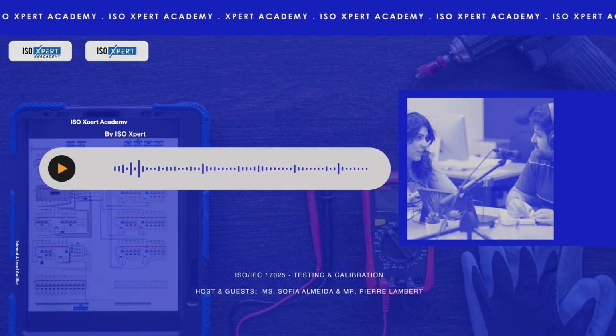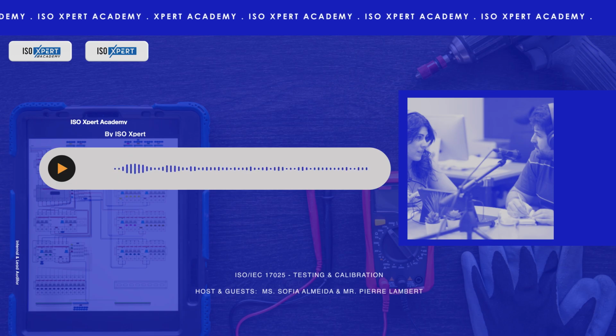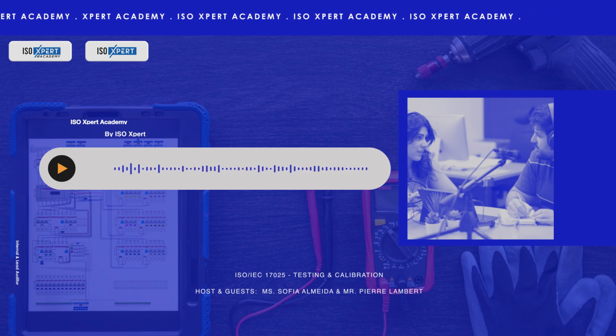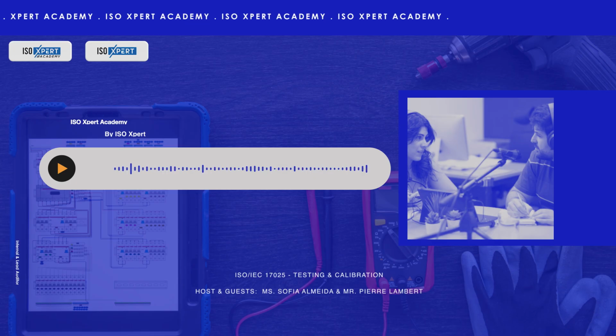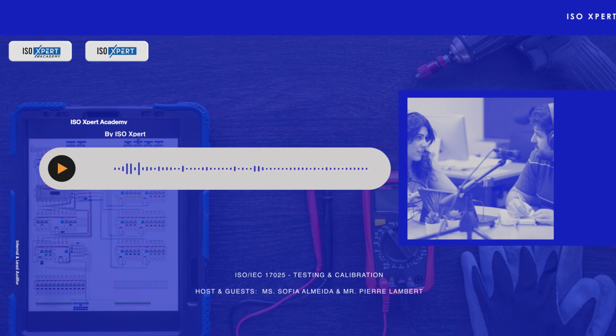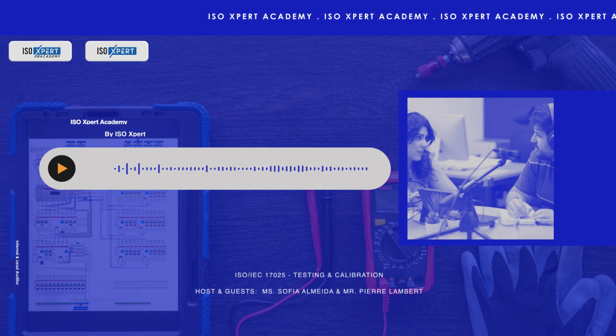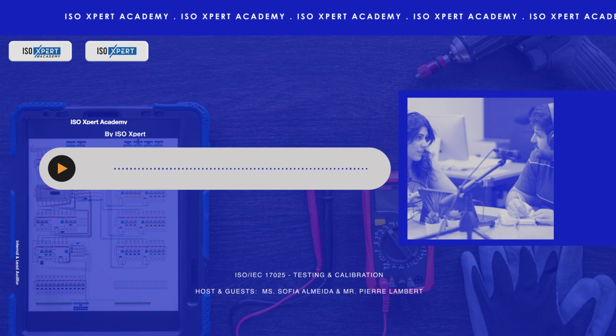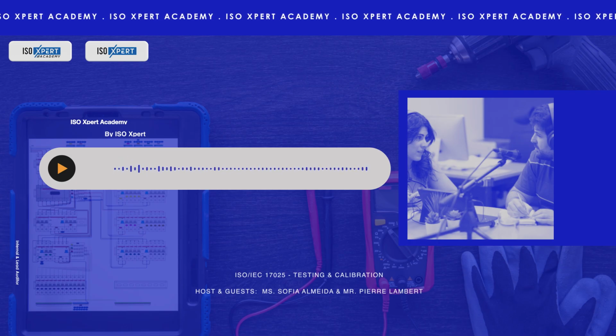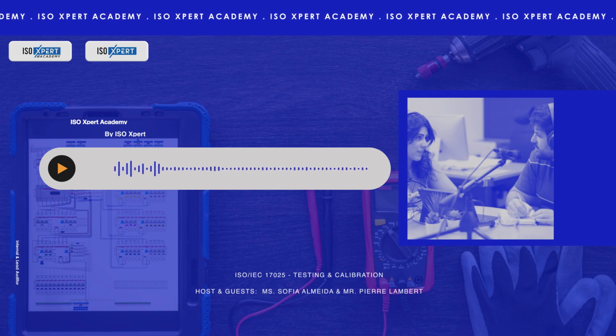Okay, and then something you mentioned earlier, uncertainty. Yes, 7.6 Evaluation of measurement uncertainty. This is critical. It's not about mistakes. It's about quantifying the inherent doubt or variability that exists in any measurement, no matter how careful you are. Where it's relevant, labs need to estimate this uncertainty. Auditors review the lab's uncertainty budgets, the calculations they use, and check that the test methods include procedures for evaluating uncertainty. It means reporting a result not just as 10, but as 10 plus or minus 0.2, for example. It's honest reporting. That distinction is so important, isn't it? Between making an error and acknowledging inherent uncertainty. It feels like a real hallmark of scientific rigor.